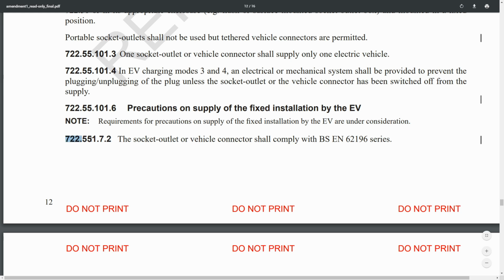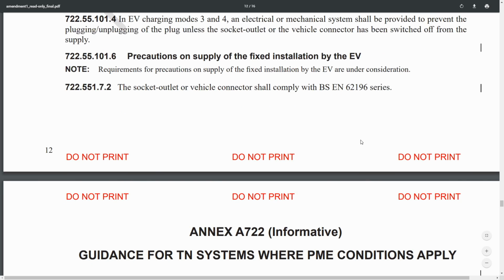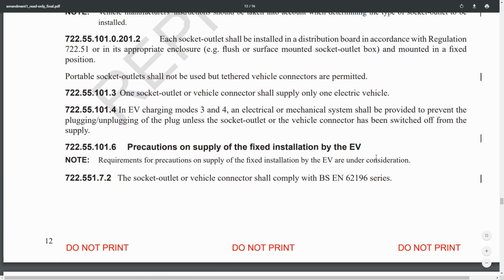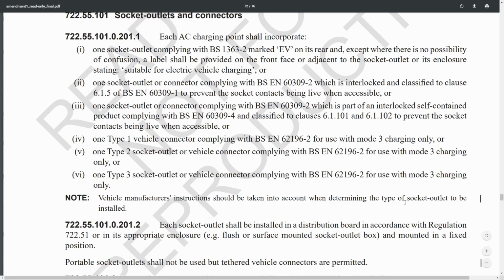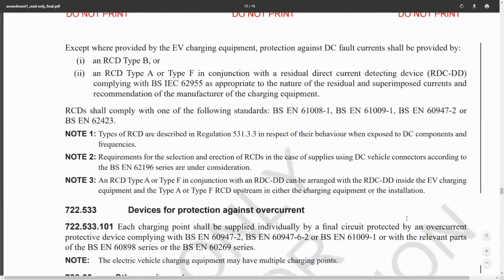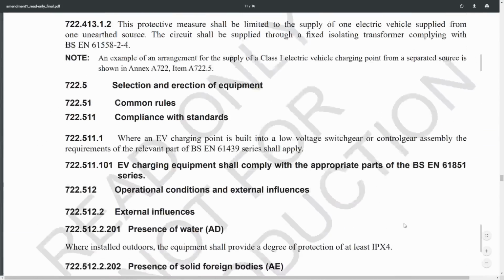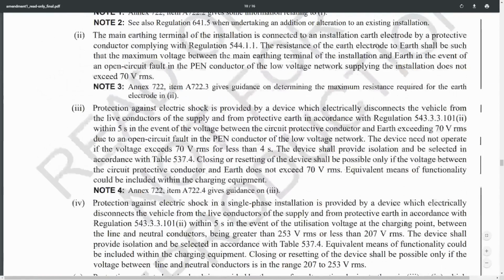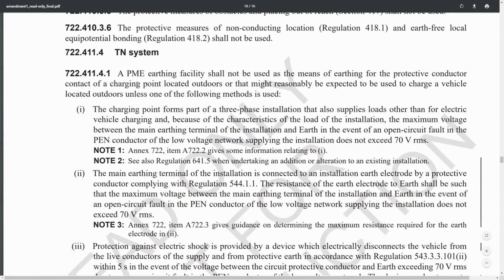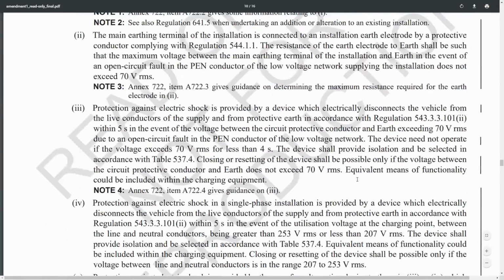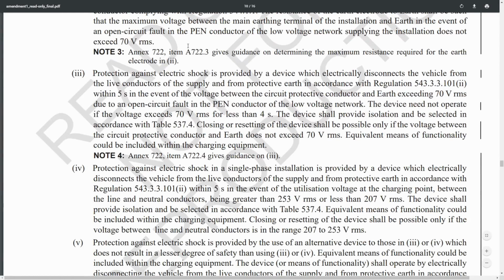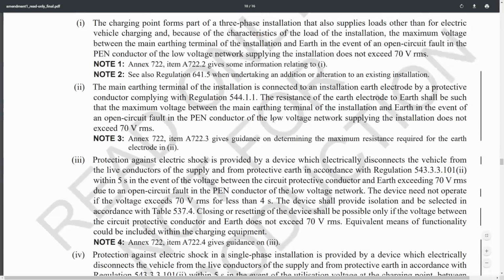This is a new one here, 722.551.7.2. The socket outlet or vehicle connector shall comply with BS EN 62196 series. So again, that's not really anything surprising there. It's just been added in as a specific word. So that is all of the changes there. So a lot of it's very minor and irrelevant, but just words altered. But the sort of meat of it is back up here with those now 5 things you can use if it's a PME earthing facility. And the most important ones are in fact the ones that have been added, because the other 3 are pretty much the same and very unlikely to be used.